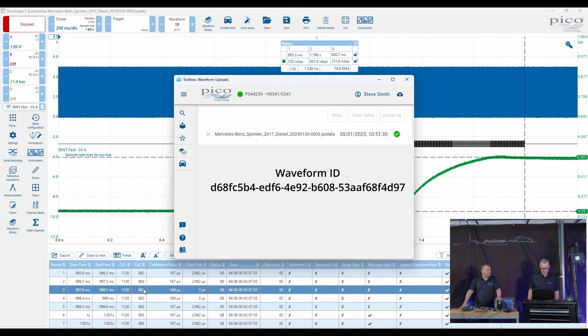Basically what we've done there is applied our network diagnostic process, our CAN process. We haven't checked if messages can be sent because it's a simple 3-wire device - I'm sure everyone watching this video is capable of that. We've gone straight to our messages being sent. Yes, but we've gone a little further with those messages, and determined not only are they being sent, but are they realistic values, do they reflect actual measurements we can take externally, much like you would do to verify any DPF pressure sensor. We've done something very similar, but with the extra step of decoding the data into human readable form.